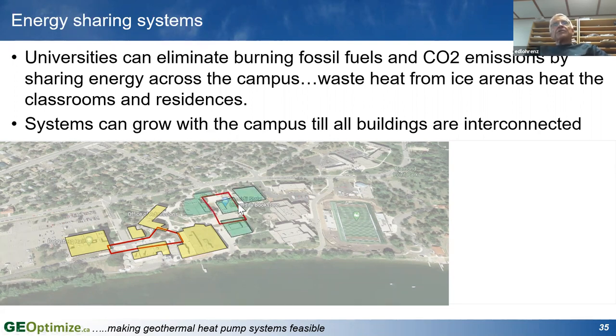Add another four buildings over here, and then you can connect those two separate loops up and gradually expand it to the whole campus. So it can be built out over a number of years in a modular way, which reduces the amount of capital cost you need up front. You can expand that system as you've got the budget and as you need to change things in the buildings anyway. So if you've got an existing building, some of these buildings are gonna have to replace chillers and boilers at some point in the next 20 or 30 years anyway.